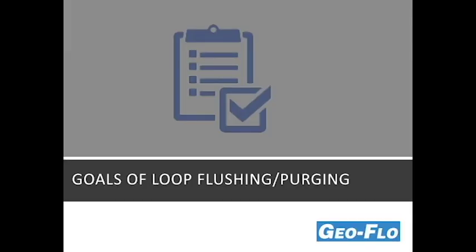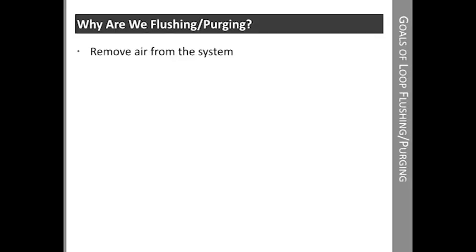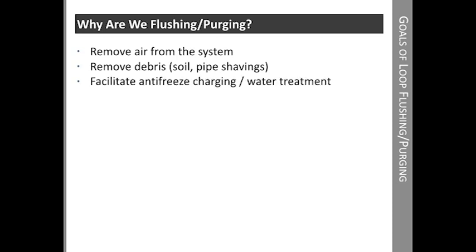Let's talk about the goals of flushing a ground loop first. Many of us in the industry just take it for granted that the loop must be flushed. However, we should consider the reasons and discuss the potential issues with a ground loop that has not been properly purged of air and flushed of debris. The first goal is removal of air from the system. We also need to remove any debris that may have been introduced during installation, such as soil or pipe shavings. Then the flush cart can assist in adding antifreeze to the system and/or water treatment chemicals.